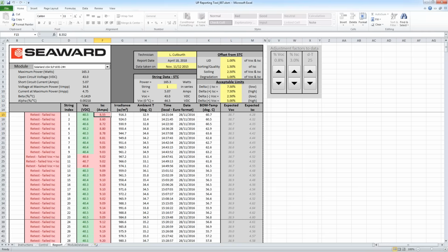Christina has asked, speaking of mega testing, what is the minimum insulation resistance required in ohms for the 1500 volt systems? The data table only includes 1000 to 2500 volt systems. It really depends on the method of insulation testing. So if you short out the circuit first, then you need a minimum of 1 mega ohm. If you don't and you're doing a point-to-point method, then we're looking at, I believe, 150 to 200. However, I think I would need to research that and get back to you with a correct answer. I don't believe those values are entirely accurate. So, Christina, I have made a note of that, and I will get back to you directly with an answer to that question.